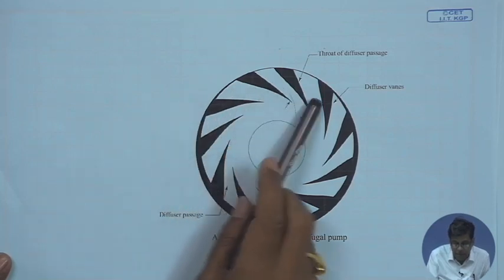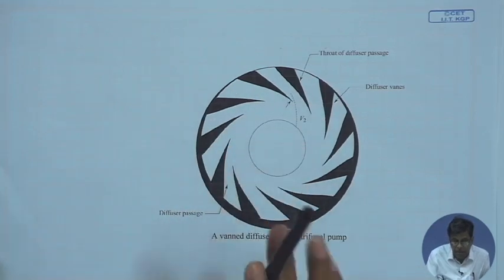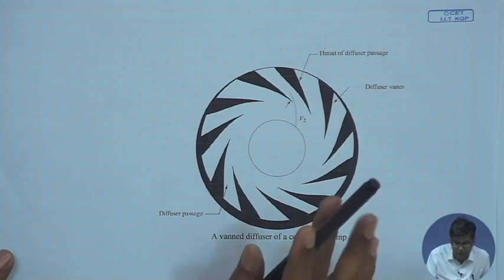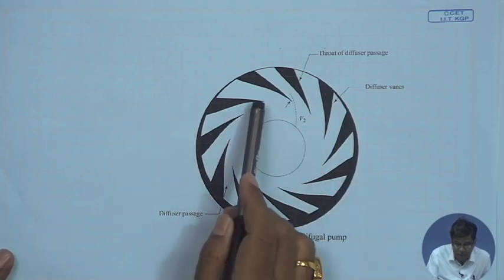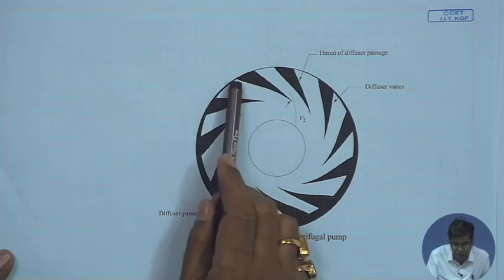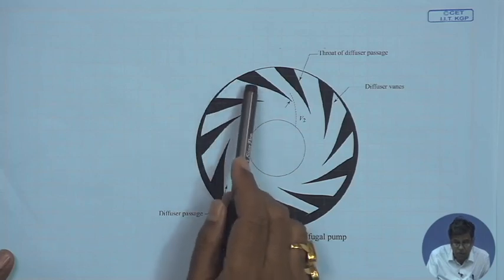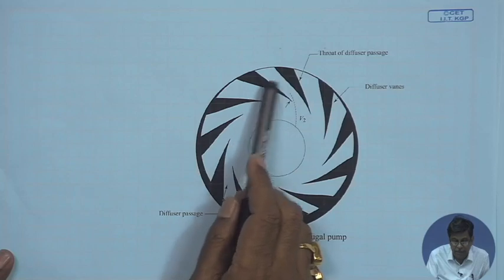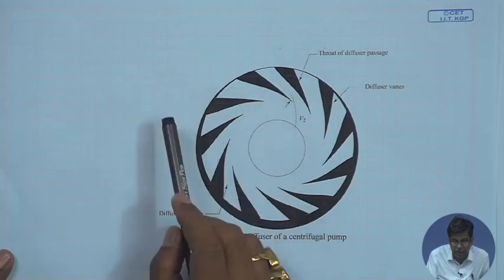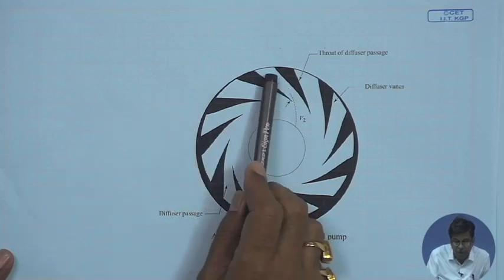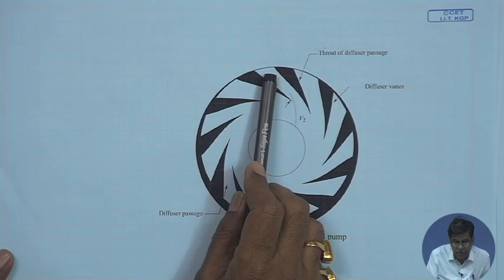While designing the diffuser vane, a few things are taken into consideration. Number one is that the angle of divergence of the diffuser vanes — that is the diffuser passage — should not be more than 8 degrees, maximum 10 degrees, between 8 to 10 degrees, to avoid boundary layer separation.